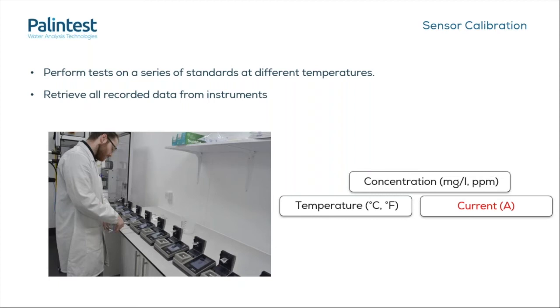I know that the title of this talk, and we've mentioned a few times, is that it's calibration free. The sensors are calibrated, but we do all that for you. So we do the hard part, so you don't have to. When a batch of sensors is produced, we take a large sample of these and perform lots of tests on a series of known standards.